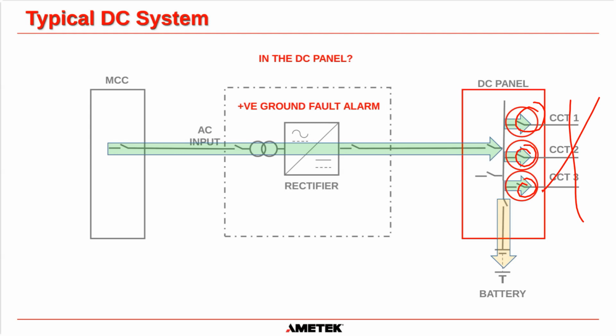If the positive ground fault stays on, yay, you found it. The ground fault is actually in the DC panel somewhere, and you would have to look for a pinched cable, or maybe a loose cable has come out and is touching ground. It's usually a pinched cable, or something has been rubbing on a sharp piece of metal in the DC panel, but it's usually definitely a cable to ground fault if it is in the DC panel.